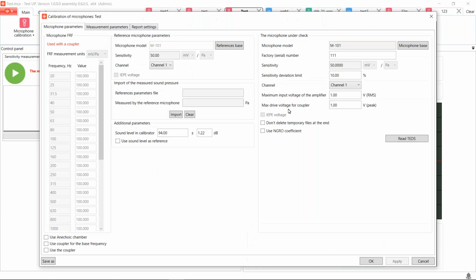Now let's have a closer look at the software interface. And first, I would like to pay your attention to the bottom of the window. Here you can choose to use an anechoic chamber if you need to perform a calibration by free field, or you can put a tick to use coupler for the base frequency, or to just use the coupler if you need to perform the calibration by sound pressure.